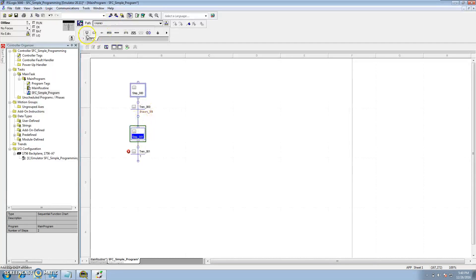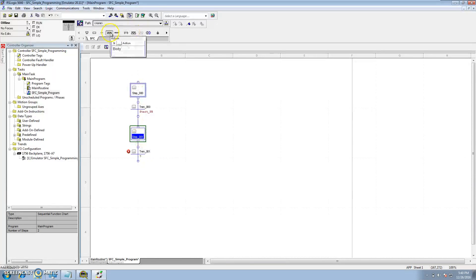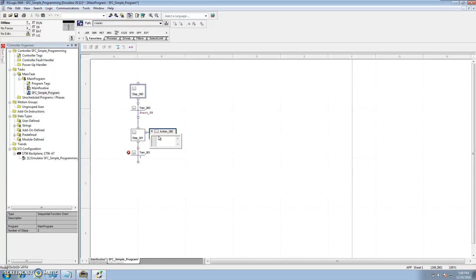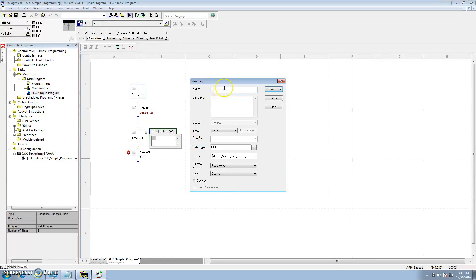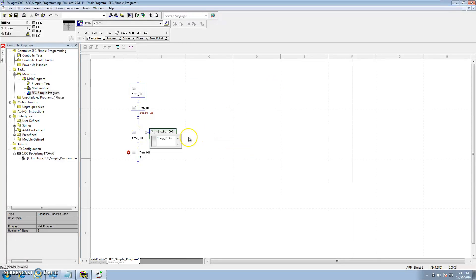Highlight step 001 and add an action body. In the action body, we want to make a series of bits, so we'll create a new tag called step_bits as a DINT so we have several of them. Then we'll reference bit 1 in that DINT and tell it to initiate bit 1, so in step 1 we'll have bit 1 turn on.